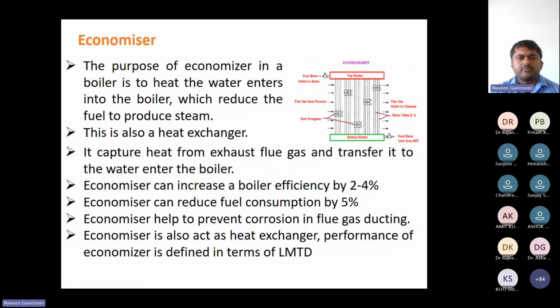So this is the economizer. Economizer, you know, increases the feed water temperature. While going through it, it picks up the heat from the flue gas, the water temperature increases, and it is supplied directly to the boiler. So it increases the boiler efficiency by 2 to 4%, reduces the fuel consumption, and prevents corrosion loss.